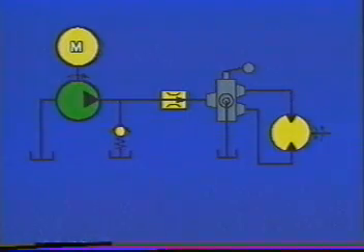Now, I'd better point out that pump flow, which does not go through the flow control valve, returns to tank through the relief valve at its setting. And that wastes energy. Looking at the brighter side, though, that same fluid could be used to perform other operations on our circuit at the same time. So another advantage of using hydraulics is the ability to use a single power source and perform several different functions simultaneously. Now, let's take a minute to recap what we've done.